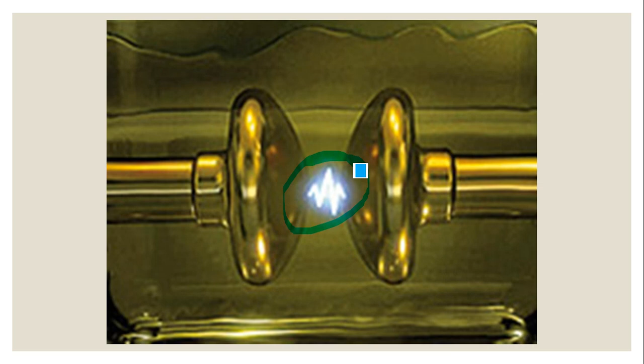So what is happening inside the chamber? This is the test equipment, and here is the chamber where voltage will be applied. It's a container containing oil, with two electrodes within a specific gap. We will be increasing the voltage across these terminals, increasing the kV gradually. The procedure will be detailed later. At a particular point there will be sparking between these two electrodes.